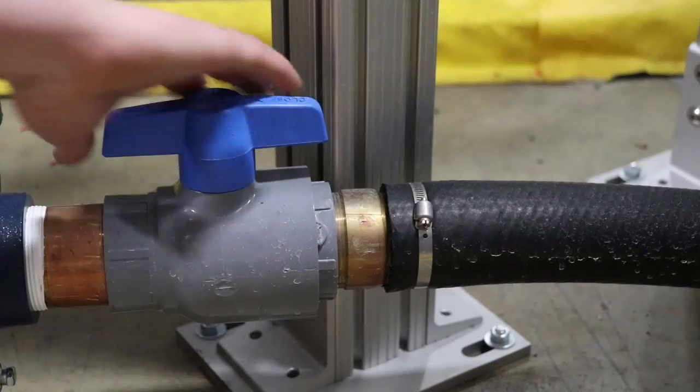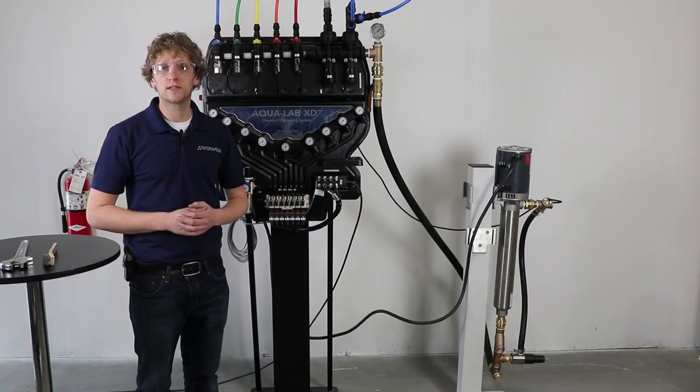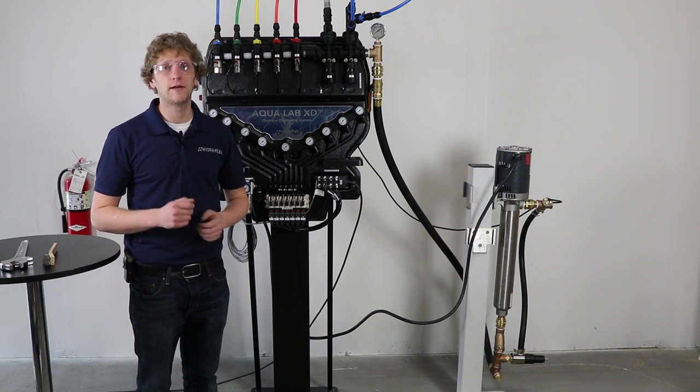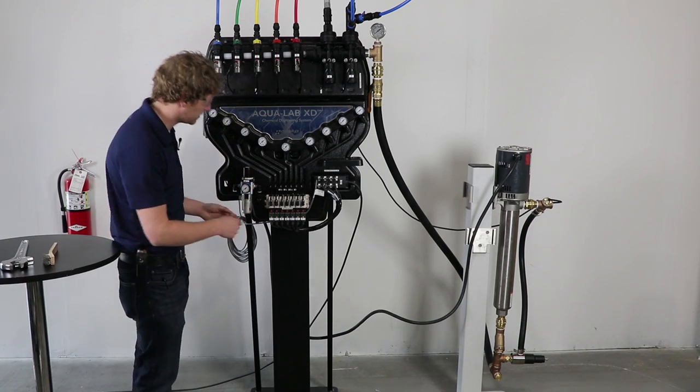First we will need to turn off the inlet water supply to the pump. Once the water supply is turned off we will need to bleed off any residual pressure by manually opening any valve by pressing the red button on the air valve located on your Aqua Lab panel.